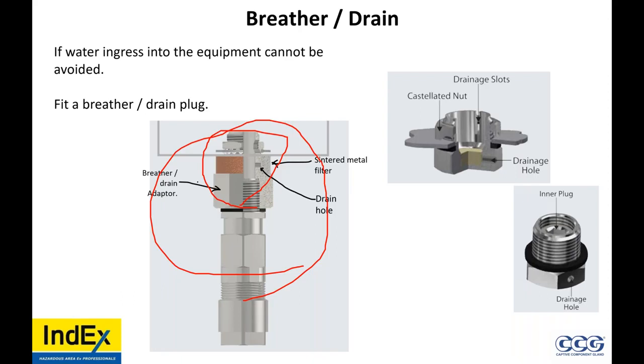The CMP gland data sheet states tapered threads guarantee IP66 for NPT. Adapters require thread paste to guarantee IP66. NPT is another thing. Without a thread lubricant, you're going to gall and cold weld your devices together. And being Canadian, we know better. We know that NPT does not guarantee IP66, such as NEMA 4X. Is it rated anywhere from IP55 to 66? There are two different types of NEMA. That's another story. So no, without lubricant, I would not trust NPT to be IP66.